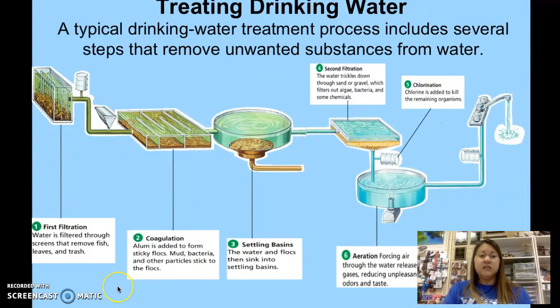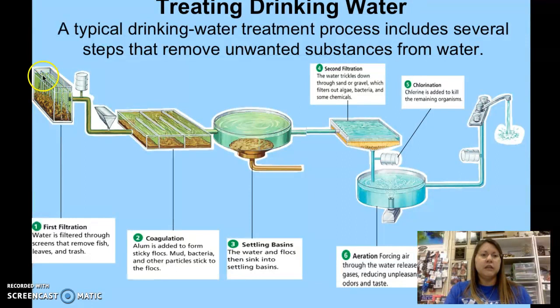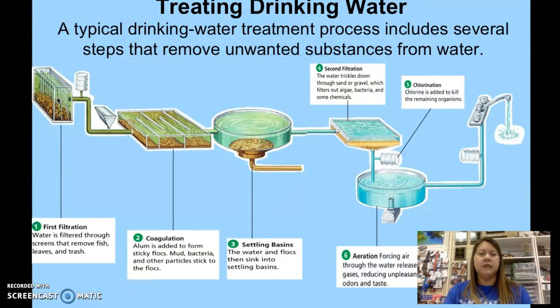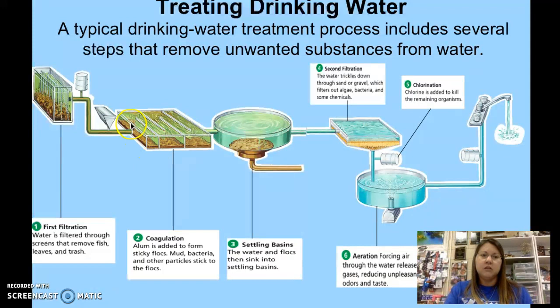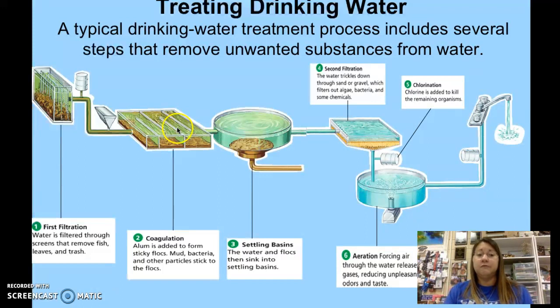The last thing is the diagram at the bottom showing the water filtration process with each different step labeled. Water enters and passes through screens — the first filtration — where big stuff like leaves and twigs are captured. The water then moves into the coagulation tank where alum is added; you can see the sticky floc at the bottom. The water moves along, allowing more surface area for more floc to be generated and more particles captured.